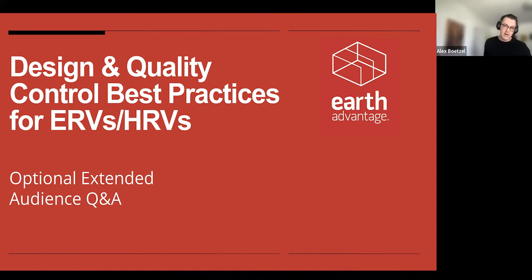It really depends on how far you take your commissioning. I think balancing the way you describe it at the unit is the minimum you should do, because we want to make sure we don't depressurize or overly pressurize the home. A little bit of pressurizing is actually our approach, pressurizing ever so slightly, because it kind of keeps contaminants out. But we don't want to do that overly, and we certainly don't want to overly depressurize the home. So balancing at the unit is important.